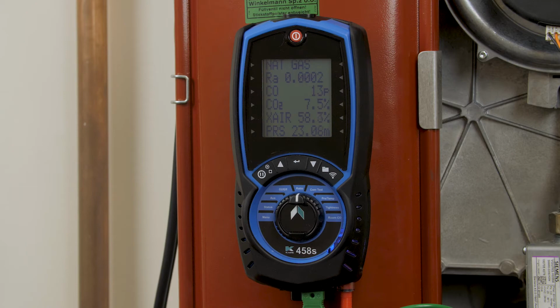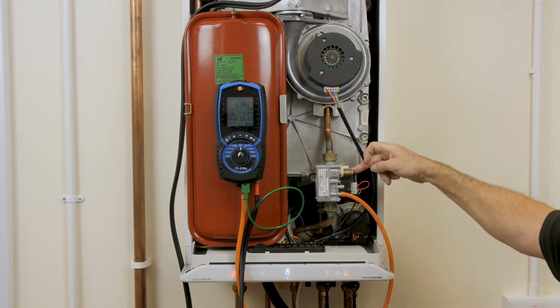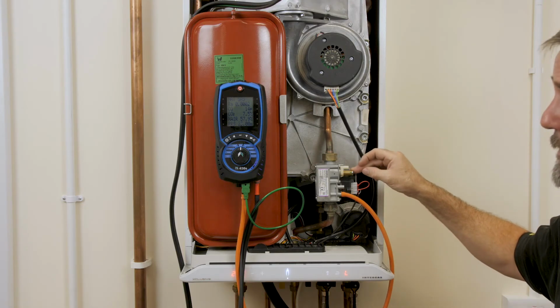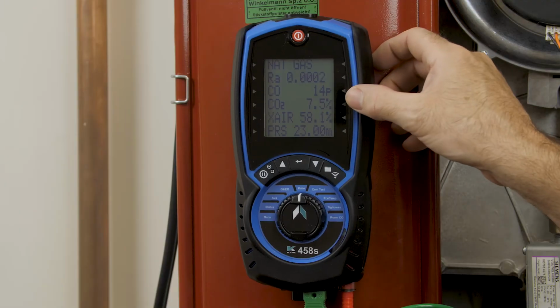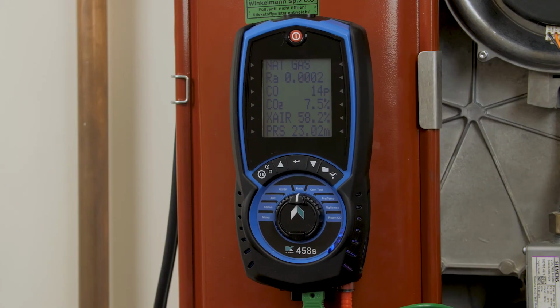Following your manufacturer's instructions, you could then set the gas valve up to the required CO2 ratio. However, we're not going to touch that today. We're just going to take the flue gas analyzer into high fire.